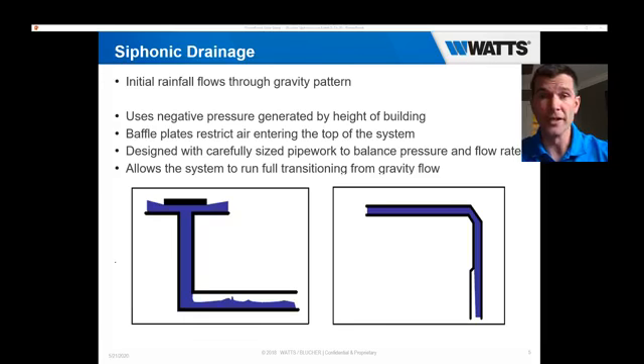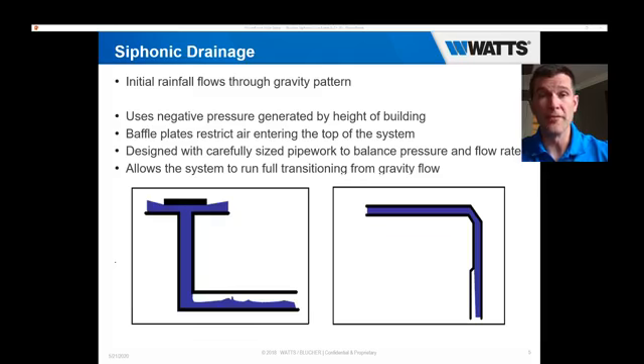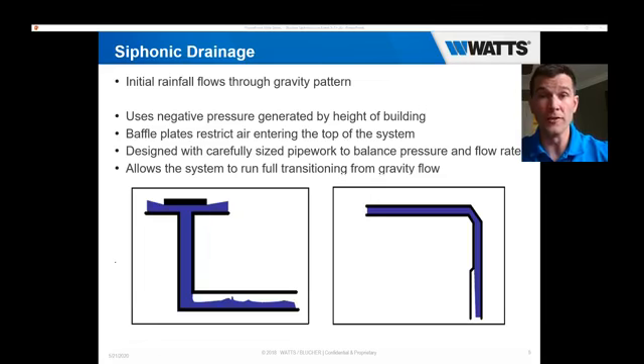From siphonic roof drainage, the initial rainfall flows exactly the same as the gravity system. With minor flow, it's acting as a gravity system going through the piping and down to drain. As rainfall increases and the ponding level increases on the roof — adding more weight to the structure — the siphonic system, at a lower water level than gravity, closes off all of the air. This allows the piping to prime itself, push out all air pockets in the pipe, and create a suction effect. Instead of a gravity system that's a third full of pipe volume, the siphonic actually uses 100%, drawing in all of the water from the roof very quickly.